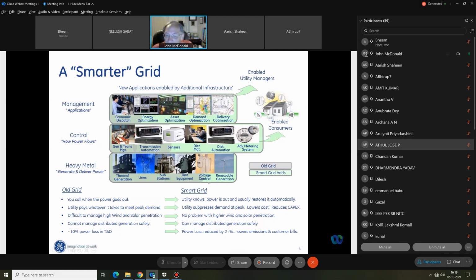So you can see on the bottom here, I've shaded voltage control halfway because we've been doing independent voltage control and reactive power control for many years. Voltage is directly proportional to load. So if we want to lower the load, we can lower the secondary voltage, right? And we do this like on a hot summer day, if it's a summer peaking utility, and if the utility doesn't want to exceed their previous peak, then we can lower the secondary voltage. Also, we can switch capacitor banks on the distribution feeders for reactive power control or VAR control.